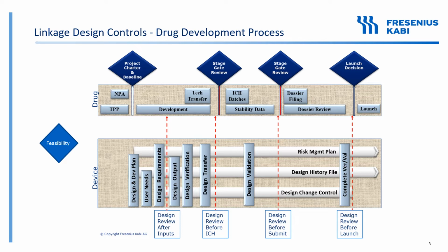So human factors assessment goes on to say, well, how close to the reference listed drug would the new concept be? So we compare the external critical design attributes and evaluate the differences. So this helps the engineering and manufacturing team determine suitable design options to consider. For example, taking into consideration the indication for use and the end users, the patient population, we may find one size doesn't fit all.